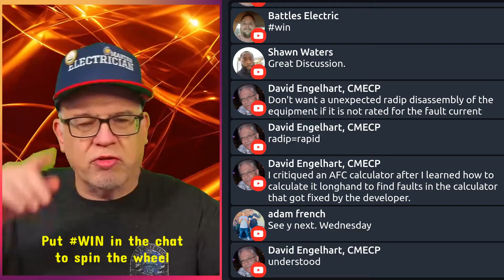All right. So anyway, that's kind of the available fault current scenario. We can do a show one day and show the structural layout of the available fault current, and we could calculate it out using Cooper Bussmann's app and that type of thing. Yep. Back in the day. Oh yeah. And that's the problem. Yeah, Dave, me too. Once you get into the weeds and understand it, you look at it as a reviewer and can't not look at it, right? But I had to make myself go, okay. Again, a quick shortcut, because I make them provide that. That's their responsibility as a plan reviewer. If the code requires available fault current numbers and the markings, they've got to provide it.